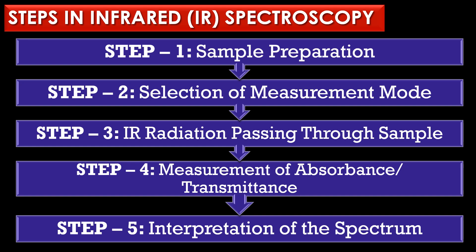The second step is selection of measurement mode. The spectrometer is set to either transmission mode or attenuated total reflectance (ATR) mode, which is ideal for solid samples or aqueous solutions. The third step is infrared radiation passing through the sample — infrared light is directed through or reflected off the sample, which absorbs specific frequencies causing molecular vibrations.